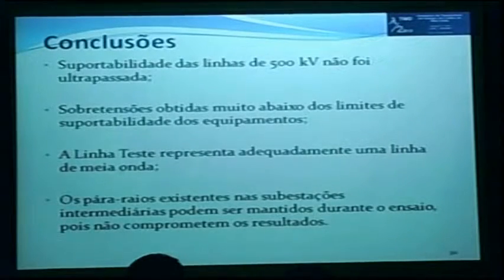In the case of direct energization without any mitigation, formed by different lines to do the different interconnections, the existing surge arresters in the intermediate substations can be maintained during the test because they are not going to compromise the results.